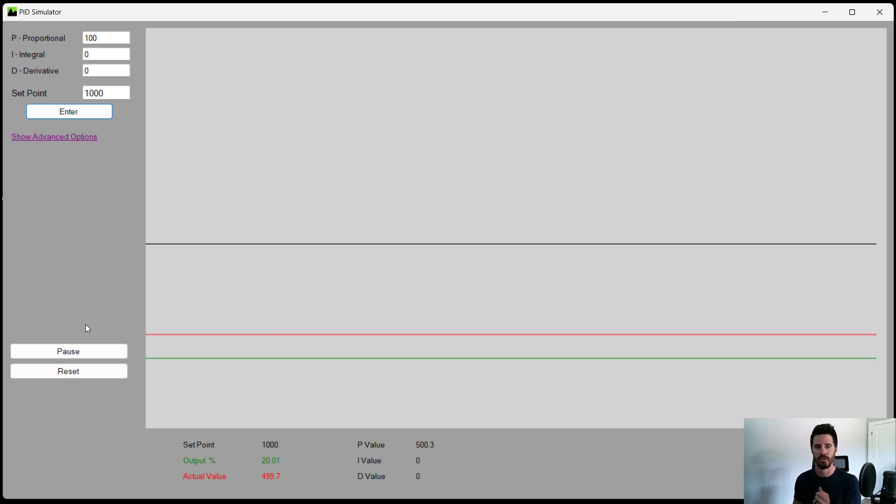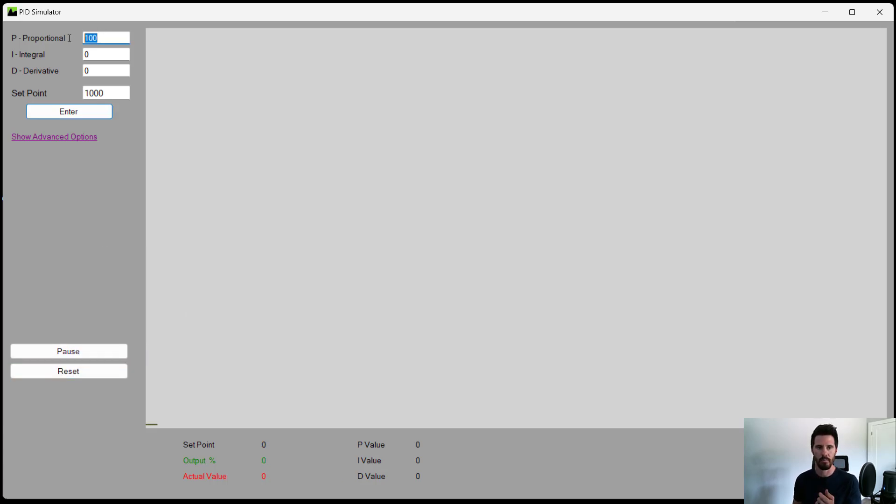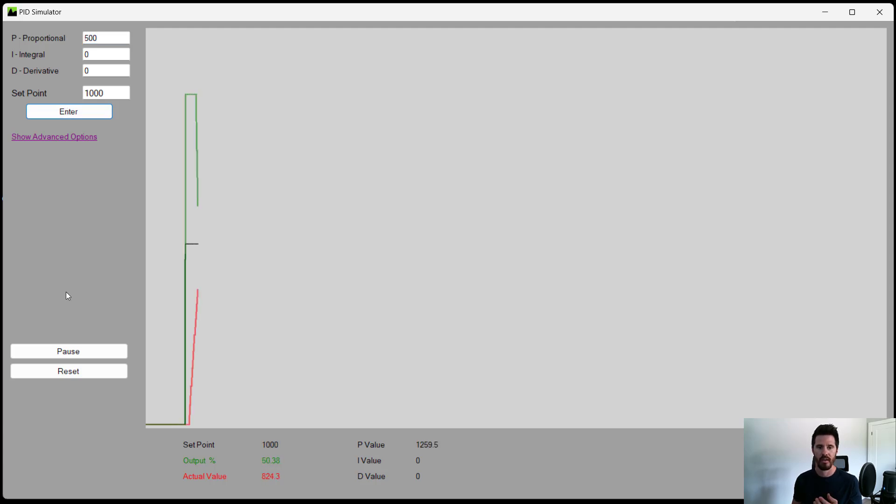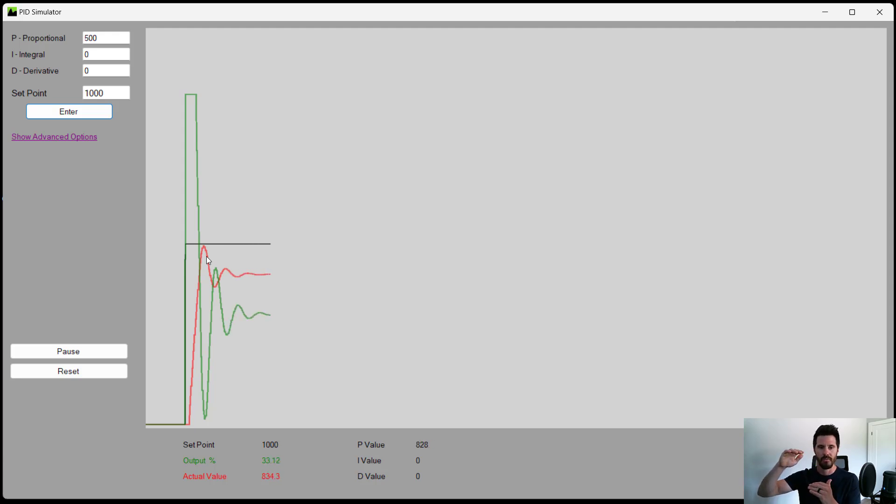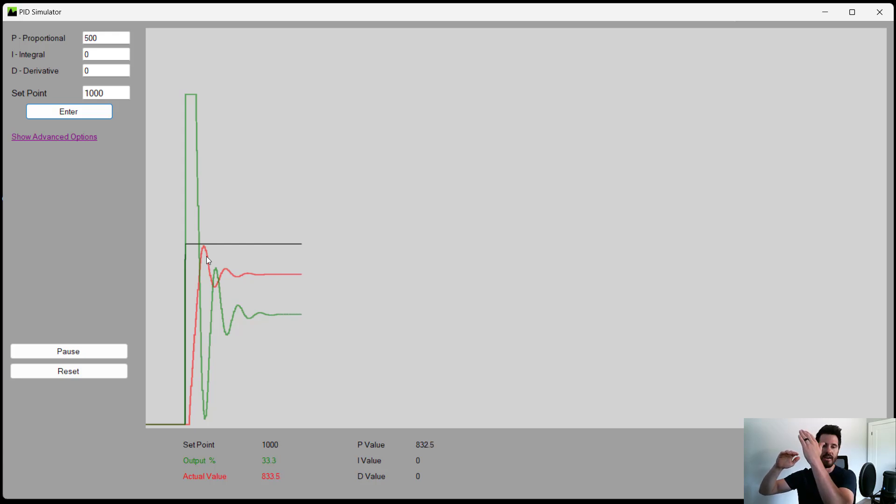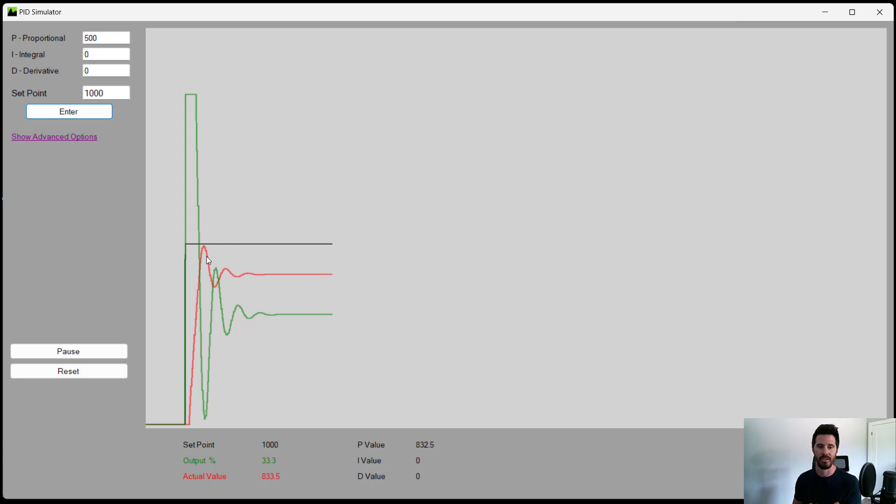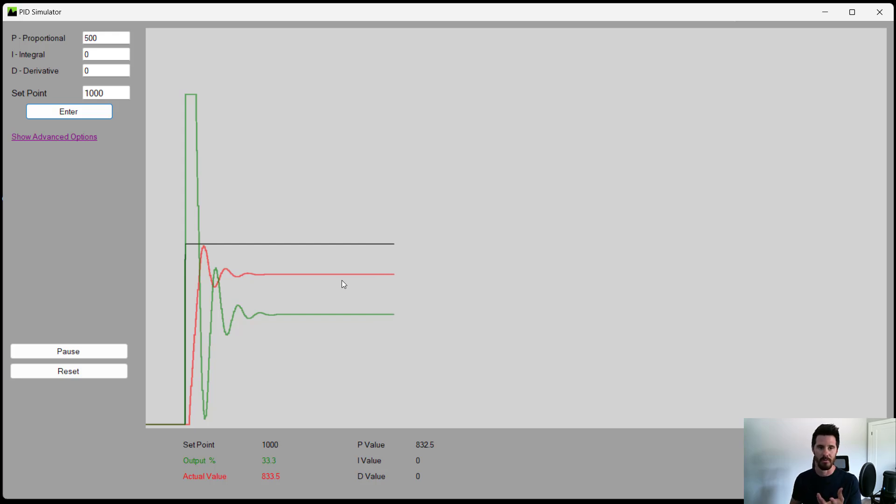And that's because our proportional is a little low. So if we put a higher proportional value, say 500. Now what you see is that initial reaction of the multiplication factor on the error of the proportional is able to bring the output high enough that it causes our actual value to come and reach our set point, but then back off slightly. So this is a good starting place for a proportional value.